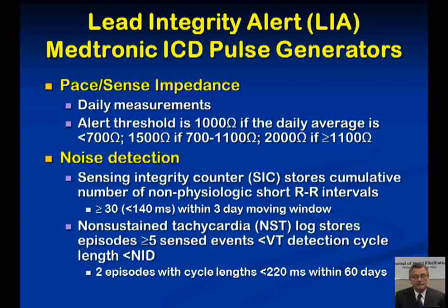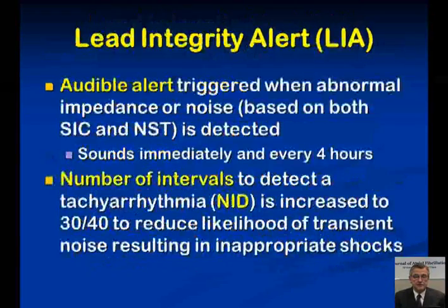It stores episodes of 5 or more sensed events, less than the VT detection cycle, and the length of the number of intervals to detect. The NST becomes positive or is triggered when 2 episodes with cycle lengths less than 220 milliseconds are seen within 60 days.